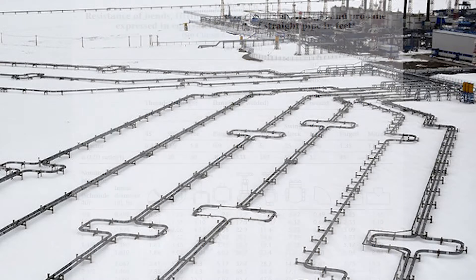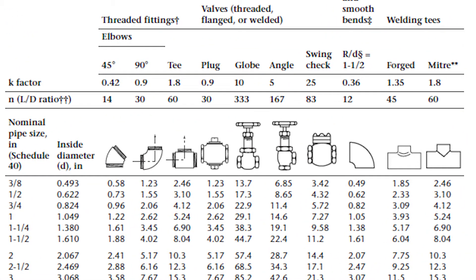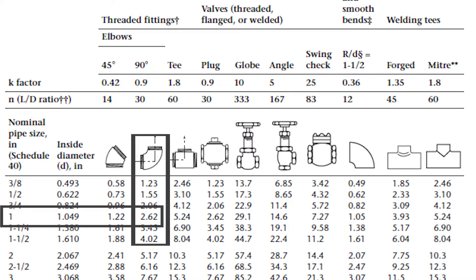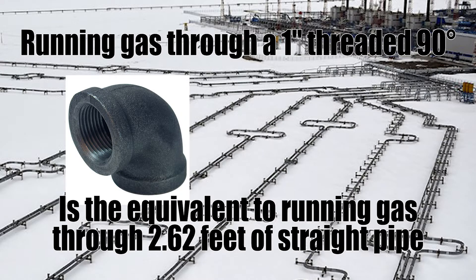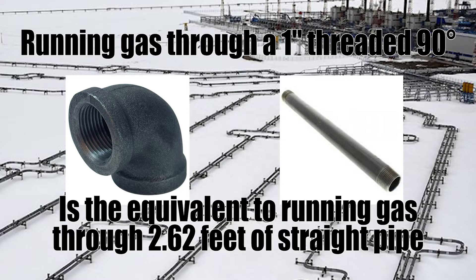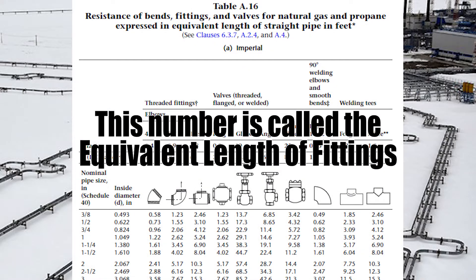The last table is Table A16: Resistance of Bends, Fittings, and Valves for Natural Gas and Propane, expressed in equivalent length of straight pipe in feet. This is the table we'll need to use to factor in for our fittings. For example, for a 1-inch 90-degree elbow, I come down to the nominal pipe size of 1 inch and across to the 90-degree elbow column, which gives me a number of 2.62. This means running gas through that 1-inch 90 is the equivalent of running gas through a 2.62-foot-long piece of straight pipe — that is the resistance experienced from it. We call these numbers equivalent length, and we'll need to factor that into the longest measured run.